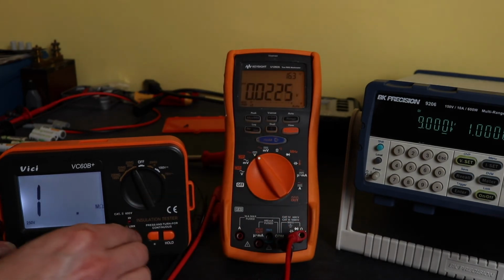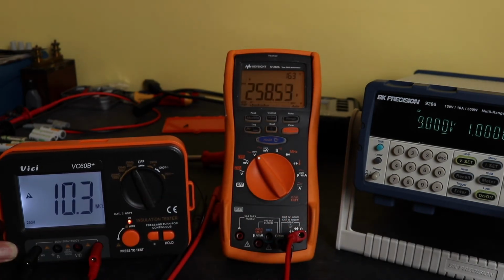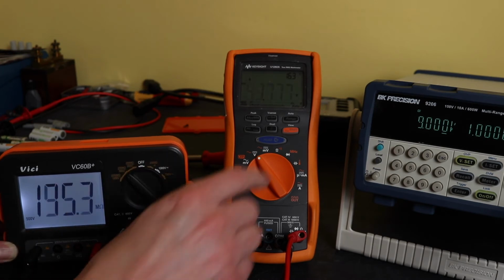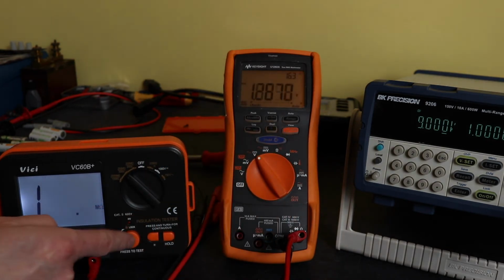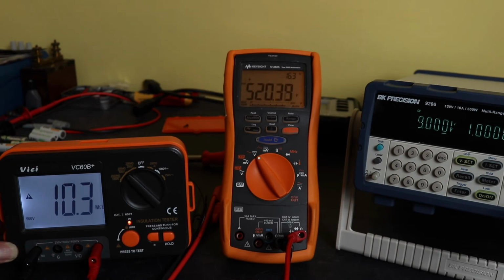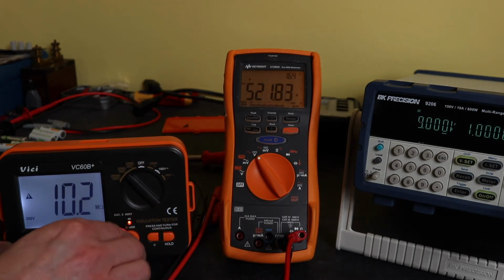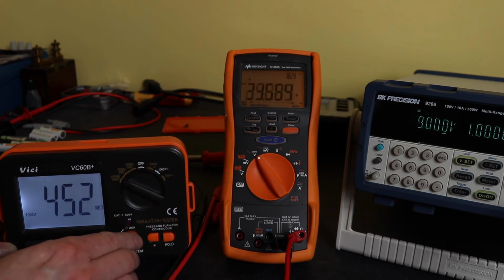We'll put the light on there, and we'll put test on, and you can see it's 259 volts. And it does creep up. Usually they go to a value and stop and don't carry on creeping up in the manner that this is doing. So that's the first issue there. And it does it on all of these ranges. 500 volts. See, 520, so we're well over the 500 volts. But again, it creeps up, creeps up, creeps up. And I'll switch it to 1000.